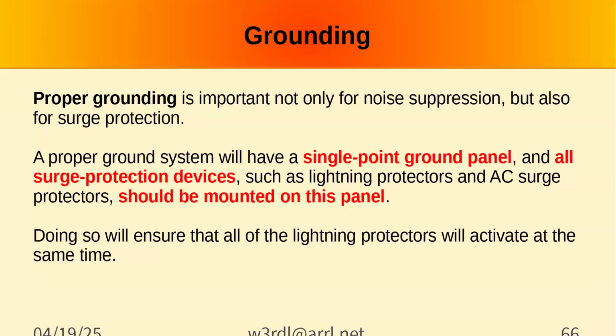I can tell you broadcast facilities don't install lightning protectors on the ground panel itself. It's a panel on the outside of the wall, everything comes into it, with a ground wire straight down. All the surge suppression on power is inside, connected in short stubs directly off the circuit breaker box. You're not supposed to put that stuff inside for amateurs, because that would mean the lightning is getting inside, unless you're talking about RF surge suppression.